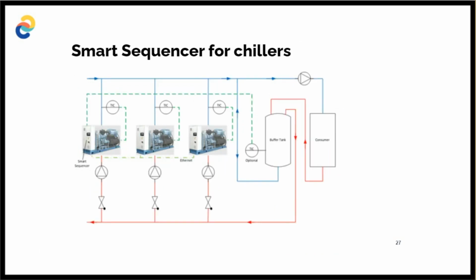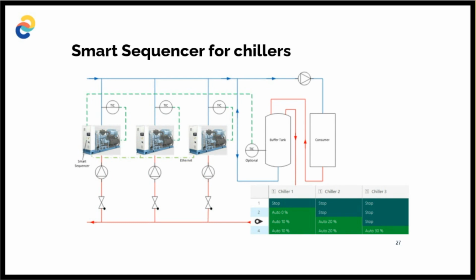The same goes for chillers. For instance, this shows 3 chillers. They can be of different sizes. It can be chilling glycol. We have a buffer tank for the control. And in this sequence, again, we're looking at maximizing the efficiency. So if we have compressors that go below 50% capacity, for instance, then we can decide to turn them off. We can decide to increase compressor speeds to give the best combination at any one time to suit the actual conditions in the plant and the actual duty that's required. It's live and it's dynamic.